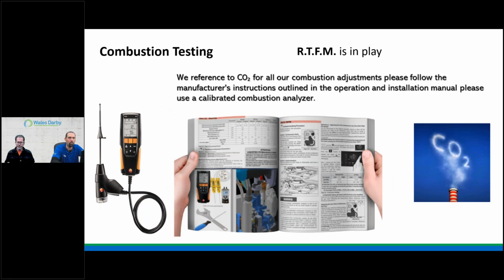The factory manual, right? Because in truth the CO2, we cannot do it by eye. You can't feel a pipe and know. You've got to use an instrument called a combustion analyzer. And with that, that is going to help us dial in with our minimum and maximum gas, fire rating, setting up the burner to be within the parameters with a little bit of extra, right? We can't be spot on. We have to be realistic that air quality changes. There are certain factors that are just out of our control.